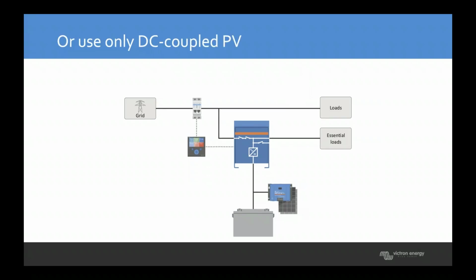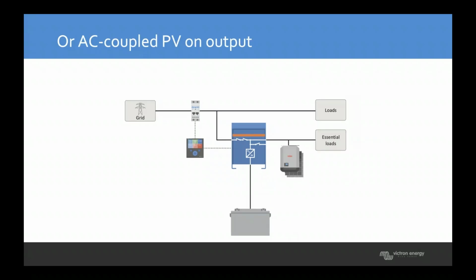It's also possible to use a DC, but we're not going to be talking about that much today. Now, with some limitations, it's possible to put the Fronius on the AC output of the Victron. So in this case, when the grid's normally connected, the grid will be providing the sine wave, which everything will connect to. So the Victron Multi-Plus will synchronize with that grid sine wave, and so will the Fronius. The Fronius AC PV will be synchronized to the same sine wave.